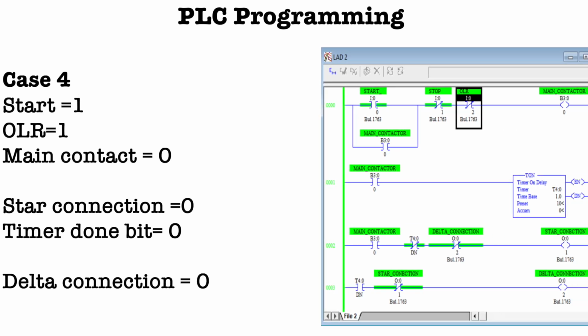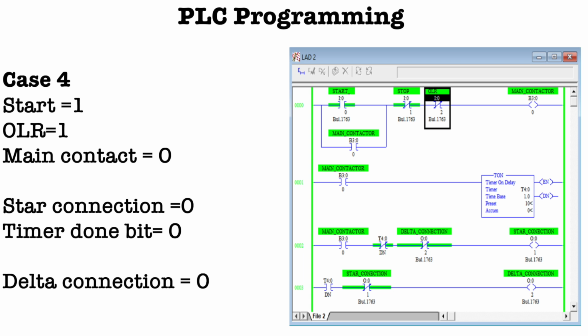Let's take the fourth case. Suppose the OLR is 1 in the running condition, meaning an overload condition happens in the running condition. You can see here when OLR is 1, the main contactor is 0 because OLR is connected to the main contactor. When the main contactor becomes 0, my T-on timer goes 0, and because the T-on timer goes 0, my star connection goes 0, right, and the motor will stop, as per the operation of the motors.